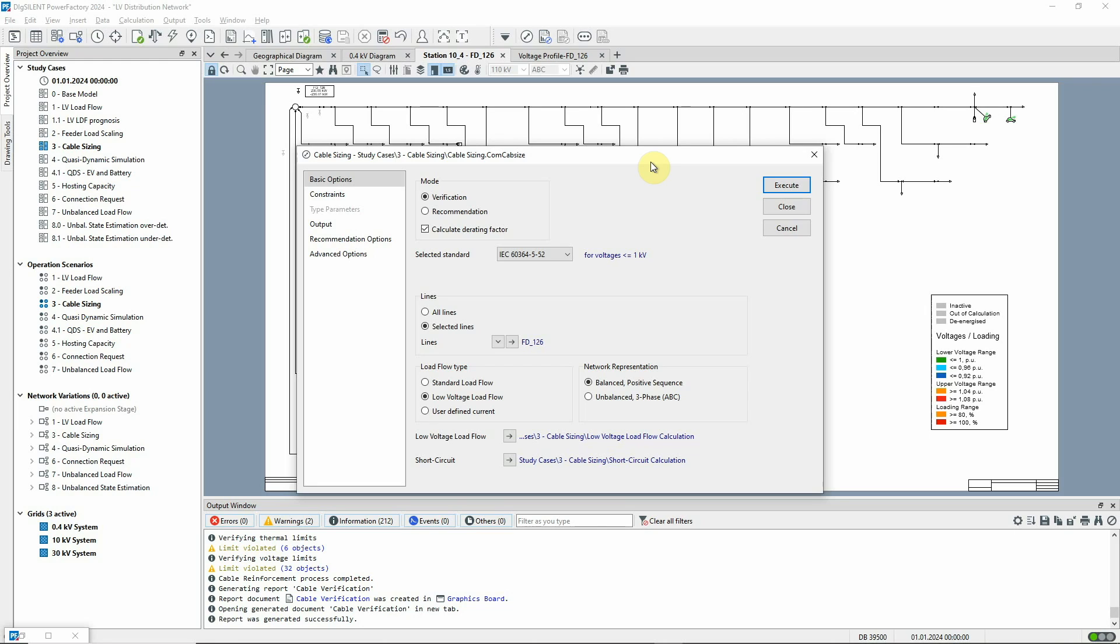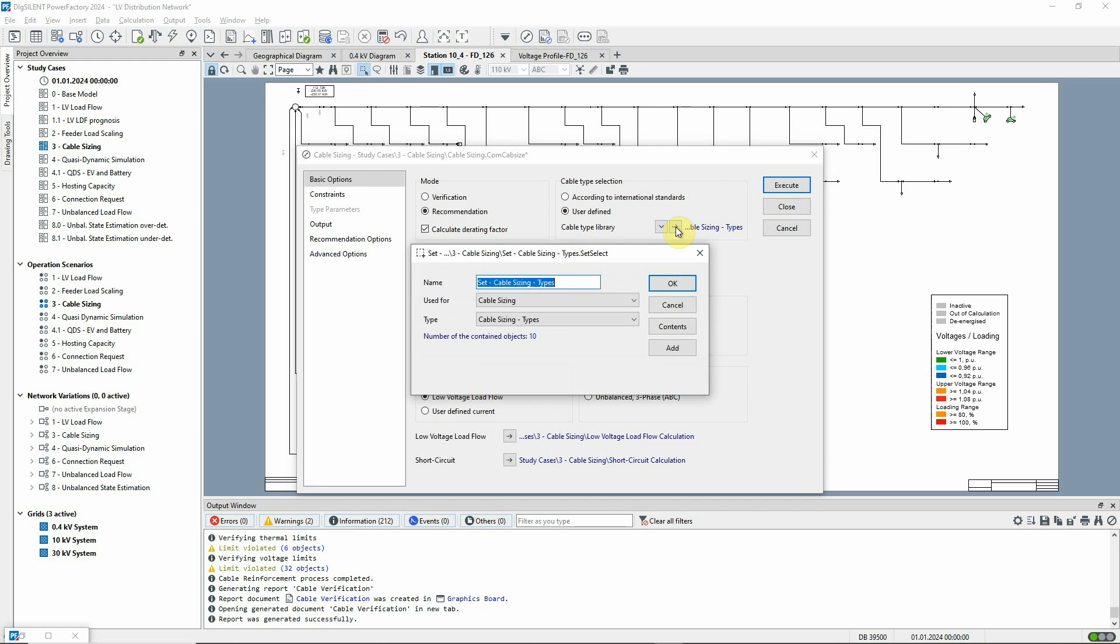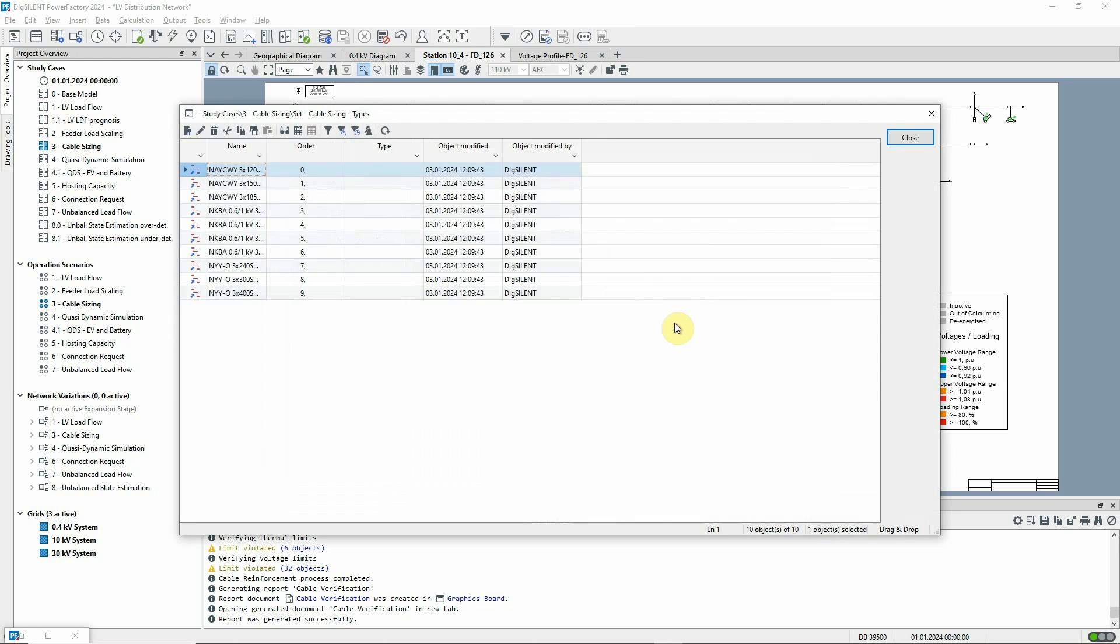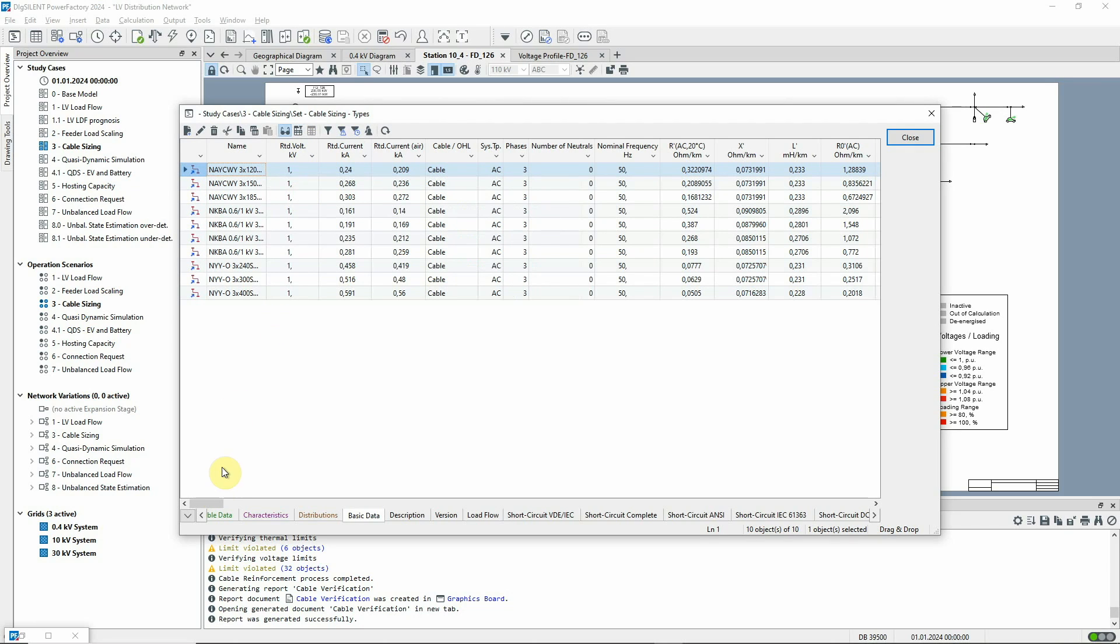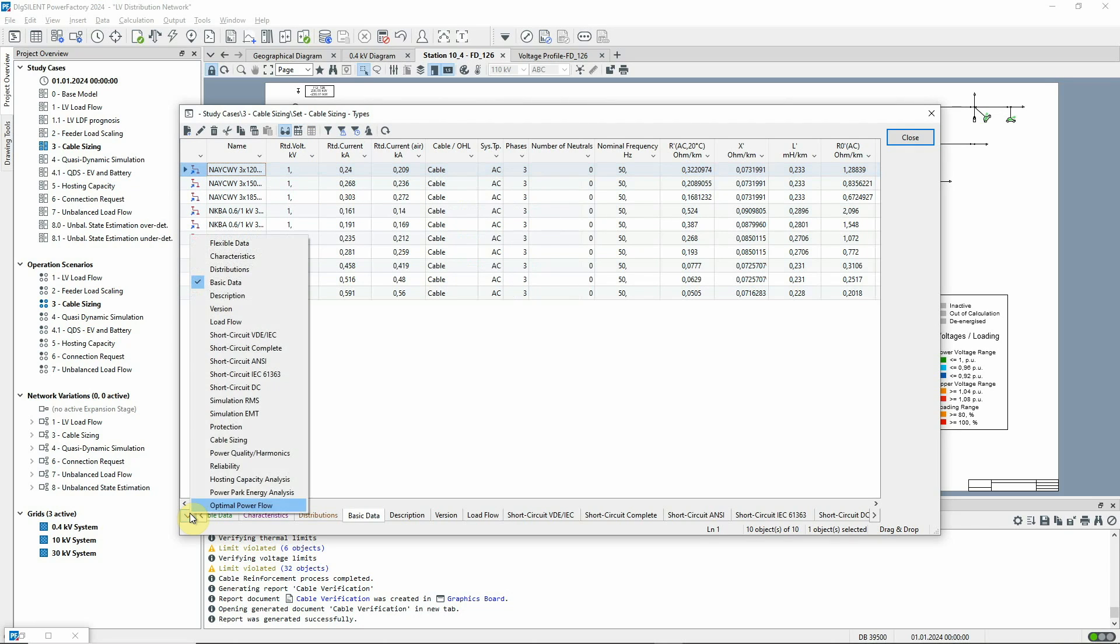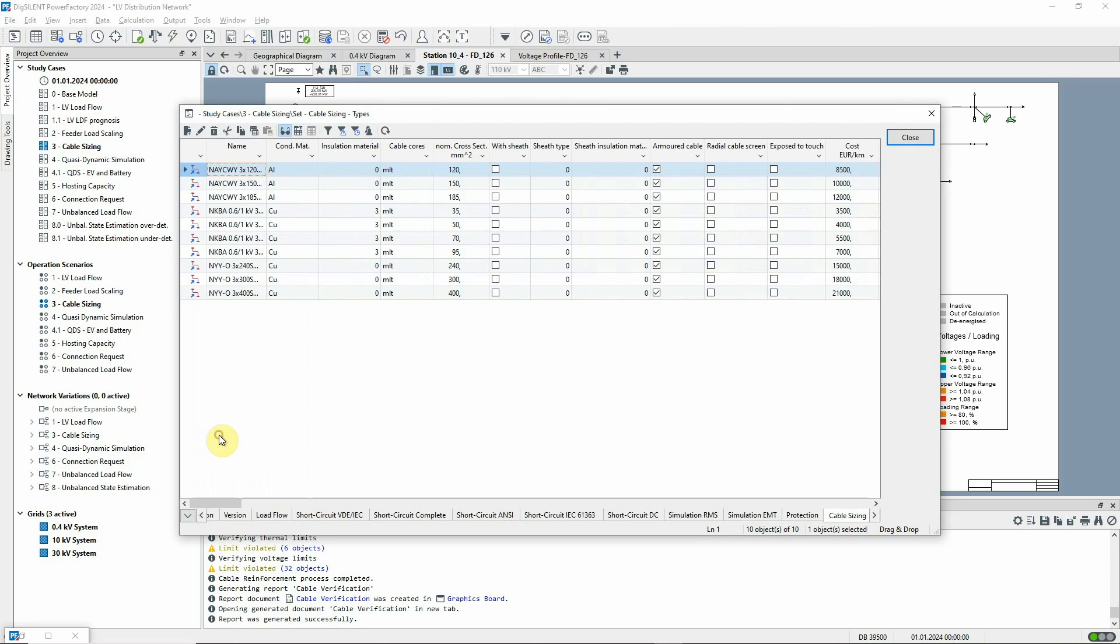We select Recommendation and will use a user-defined selection of cable types held in the project. As well as all the technical parameters, note that costs have been entered which will be taken into account when cable types are selected by the cable sizing tool.